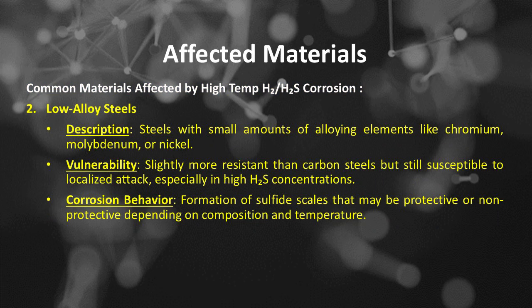The affected materials, number 2, is low-alloy steels. Steels with small amounts of alloying elements like chromium, molybdenum, or nickel. The vulnerability of the low-alloy steels: slightly more resistant than carbon steels but still susceptible to localized attack, especially in high H₂S concentrations. Corrosion mechanisms commonly affecting the low-alloy steels: formation of iron sulfides, prone to sulfidation and hydrogen embrittlement. The corrosion behavior of high-temperature hydrogen or H2 and hydrogen sulfide or H₂S corrosion on these low-alloy steels is formation of sulfide scales that may be protective or non-protective depending on composition and temperature.